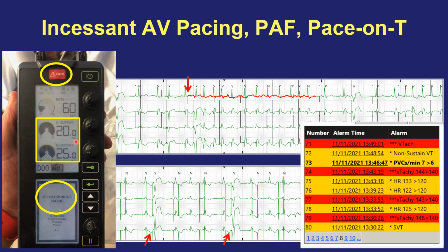So the combination of asynchronous pacing and high output pacing while there are native beats occurring, there's a formula that leads to proarrhythmia. So this was an accident. Somebody had accidentally at the bedside hit the DOO button, was not aware that that had occurred, and that resulted in this continuous DOO high output pacing. And then of course, the moment that this was restored back to DDD pacing with appropriate sensitivity, these proarrhythmia episodes stopped occurring because pacing was only occurring as needed and not on top of native beats.